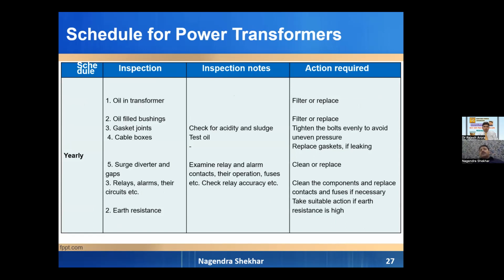If we find any kind of unusual or unexpected result, we have to either change or replace. We have to tighten bolts every year so that tracking between two connectors, that is lugs and sockets, does not occur. Gaskets we need to replace if leaking, and if any action is required on our protection relays, we have to replace them or test their functioning.